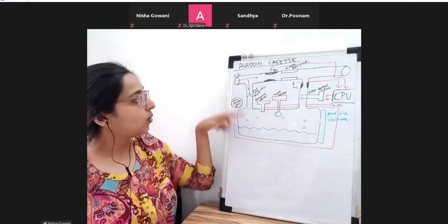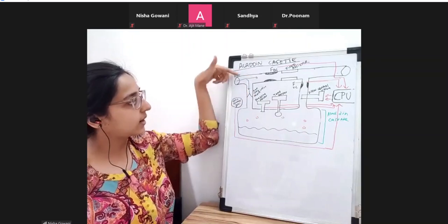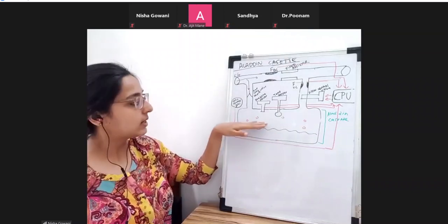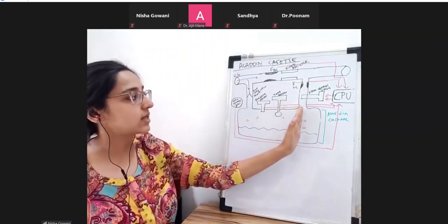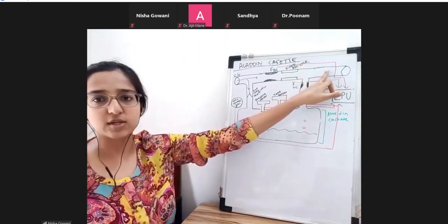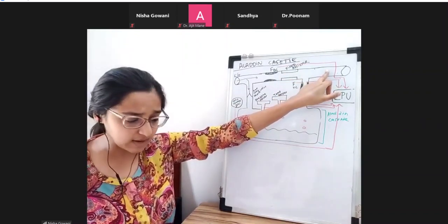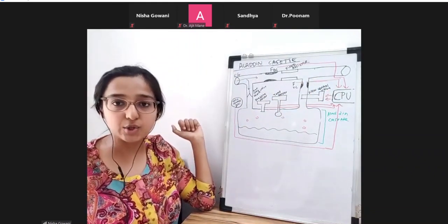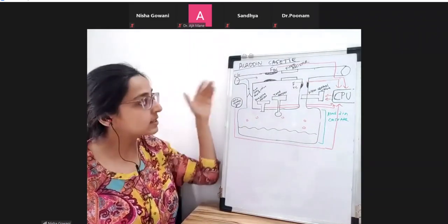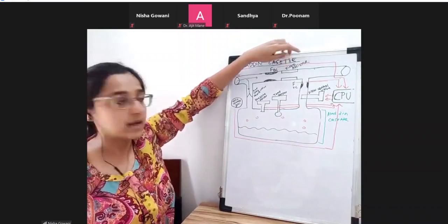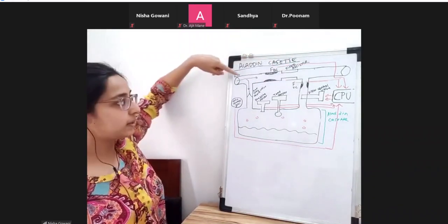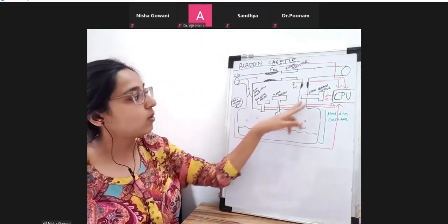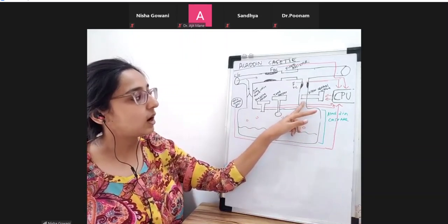Now what is happening over here? Fresh gas flow is getting split. Some amount of fresh gas goes through the bypass, and some comes through the vaporizing chamber. The gas laden with vapors will start exiting and will join the fresh gas, the same as we already know. Now, who is going to determine how much the split occurs? There was a splitting ratio in the variable bypass. So here, the splitting will be decided by the fixed resistor, which will determine the split between the bypass and the vaporizing chamber.